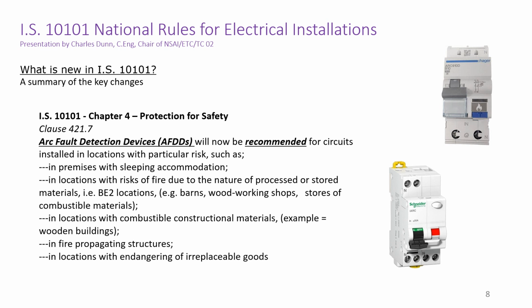For this reason, arc fault detection devices, AFDDs, will now be recommended for circuits installed in locations with particular risk, such as in premises with sleeping accommodation, in locations with risks of fire due to the nature of processed or stored materials, i.e. BE2 locations, e.g. barns, woodworking shops, stores of combustible materials. In locations with combustible construction materials, for example wooden buildings. In fire propagating structures, in locations with endangering of irreplaceable goods. Don't forget, the wording is recommended. AFDDs are not yet mandatory.